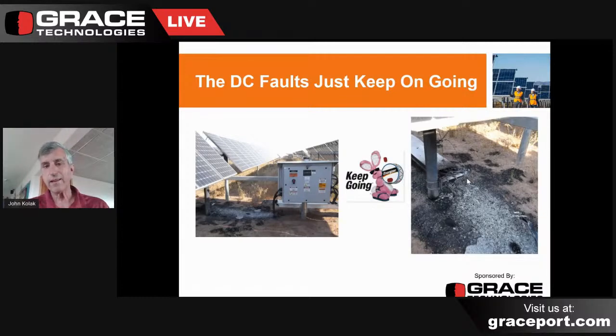So if you actually calculated incident energy, it would calculate to several hundred calories of exposure. So while you would think that would be unsafe at any speed to work around, in real life, the arc blast part of it is not very significant. And so this is absolutely high calculated incident energy, but the difference is, from a safety perspective, its blast potential is quite low. And if you did have an arc flash in those situations on that part of the system, it usually doesn't result in a very significant arc flash hazard because you are able to self-rescue. Let's go to the next slide.